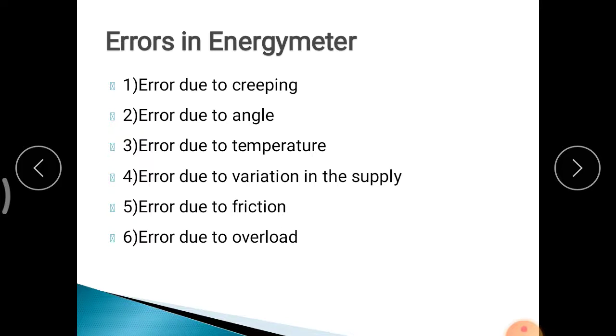Errors in the Energy Meter: First, error due to creeping — the disc should rotate only when connected to a load. But sometimes, even without a connected load, the aluminium disc starts to rotate. This is called creeping error, as the disc is consuming energy when it should not be rotating.